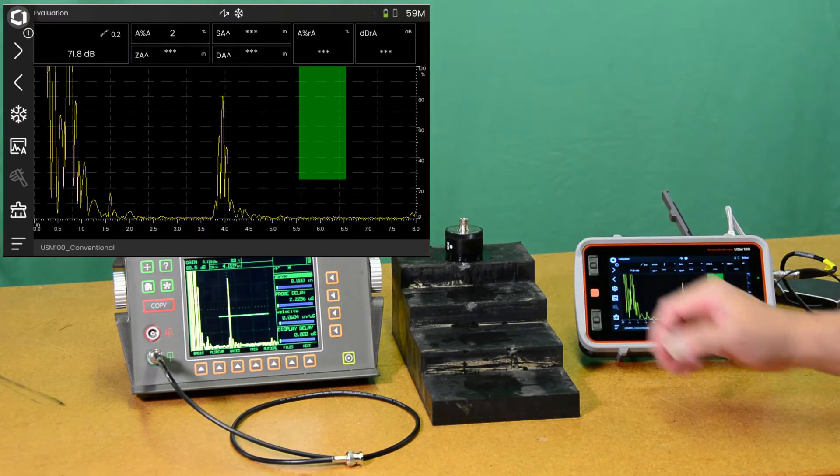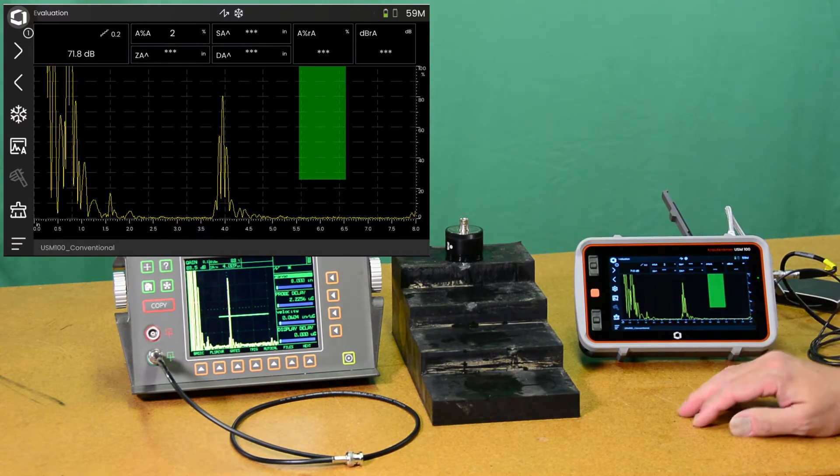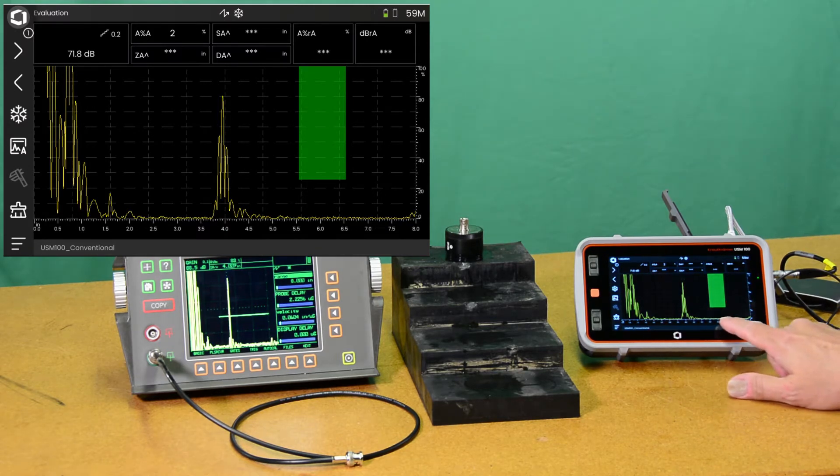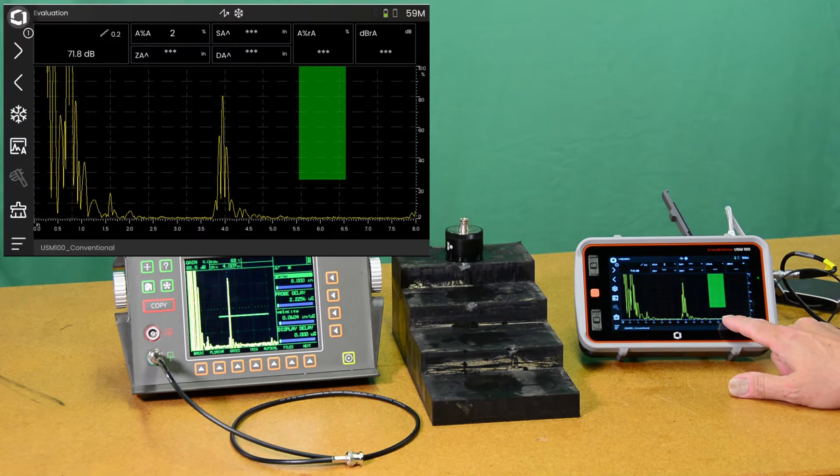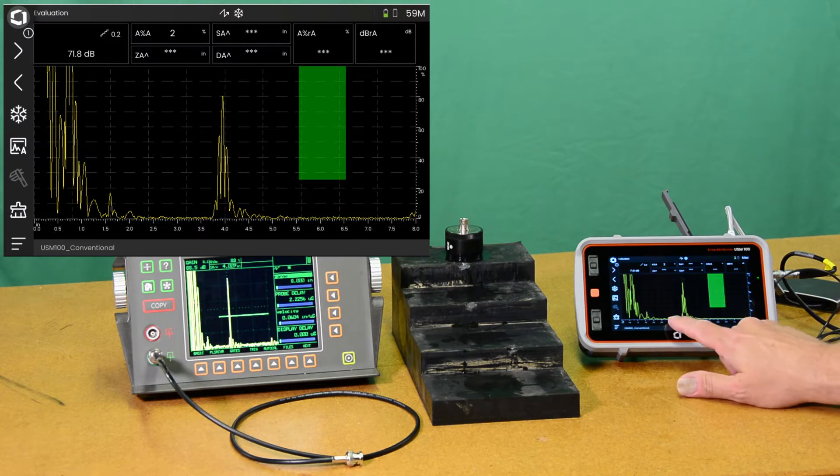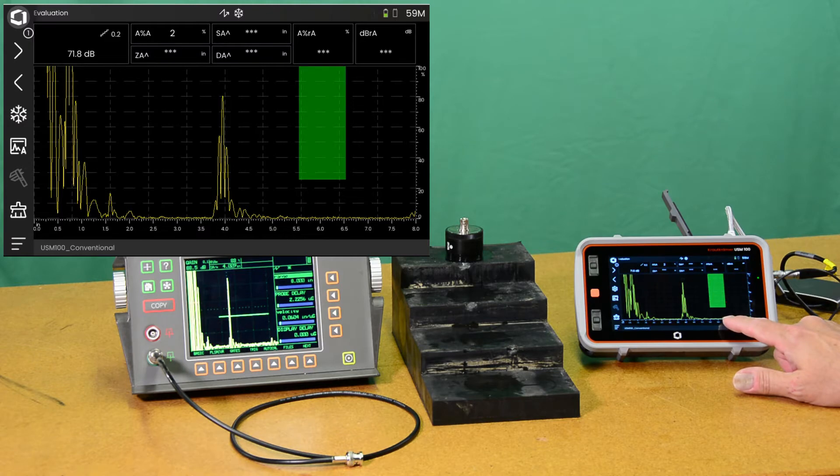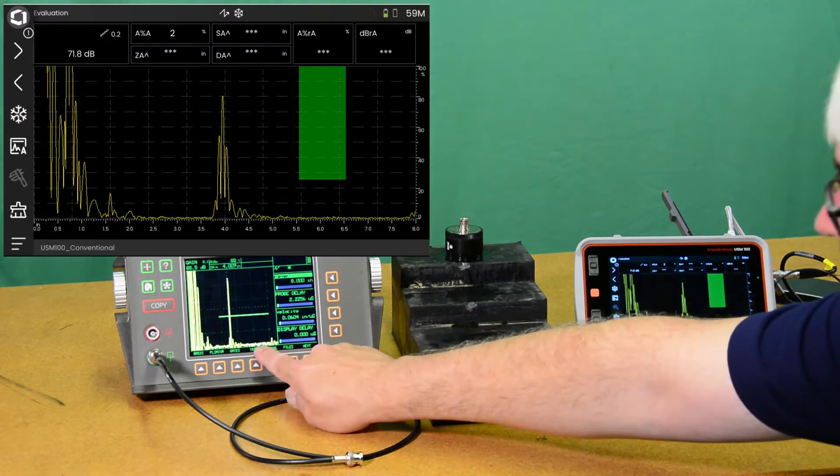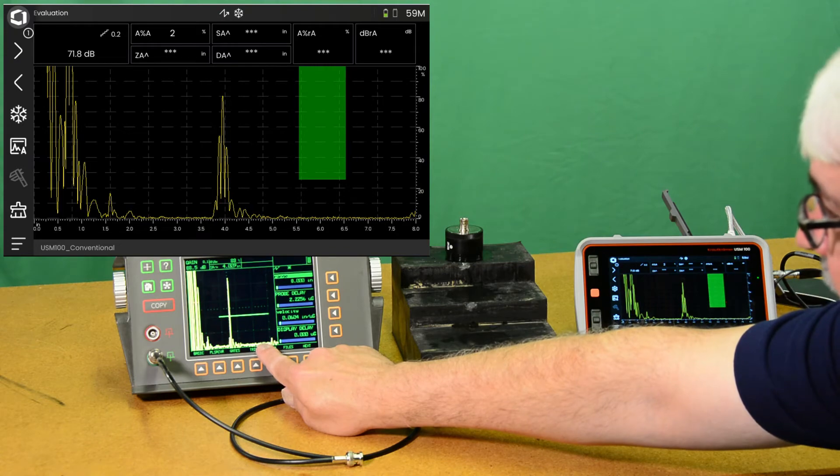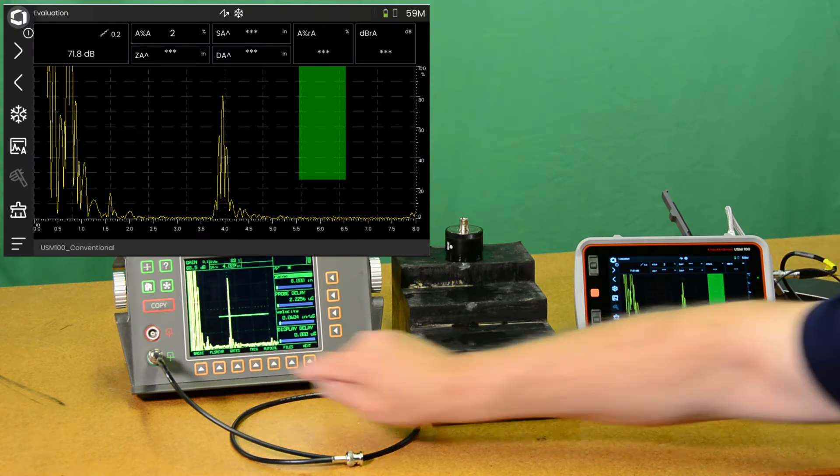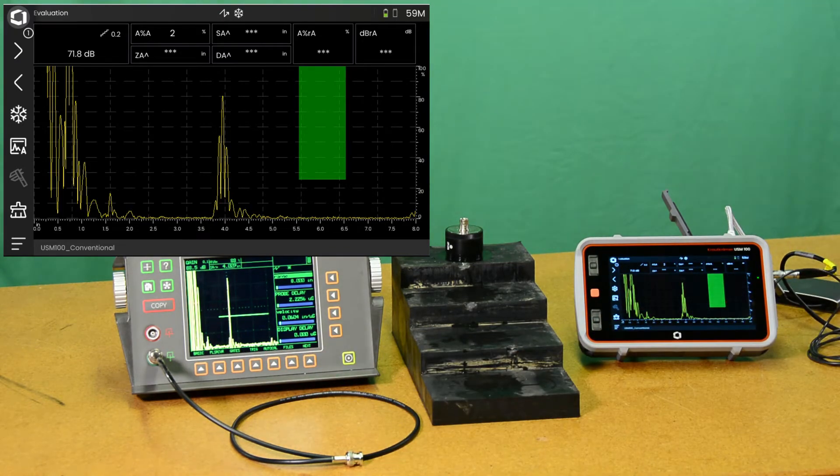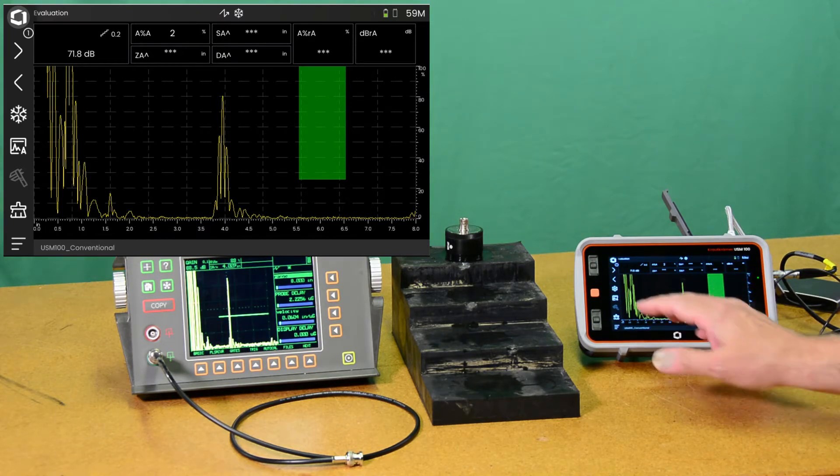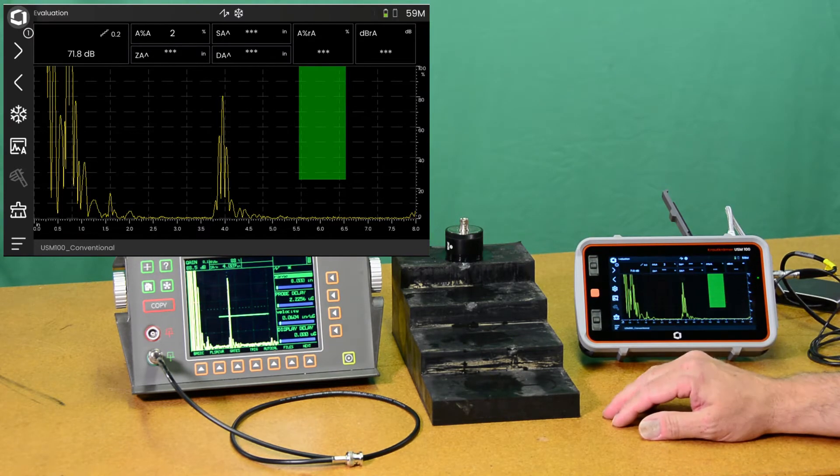So again, on the left the USM-60, on the right the USM-100. You can see in the USM-100 our noise floor is lower, it's only a couple of percent screen height. The basic noise floor of the instrument is still very quiet down below two or three percent. Here in the USM-60, you can see a higher noise floor that's about four or five percent, some of it peaking closer to eight or nine percent. Just overall quieter and making more efficient use of the probe.